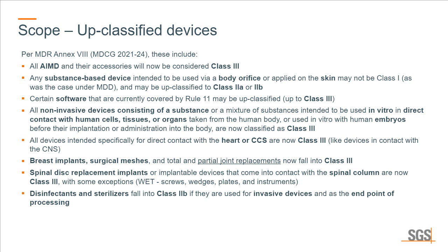Disinfectants and sterilizers fall into class 2B if they are used for invasive devices and as the endpoint of processing. Previously, it was mostly just implants, but now disinfectants and sterilization chambers, if they were used for implants, they were class 2B. Now it's for all invasive devices. So again, the range has been extended there.